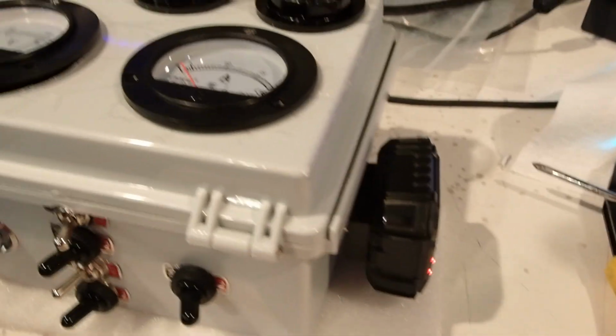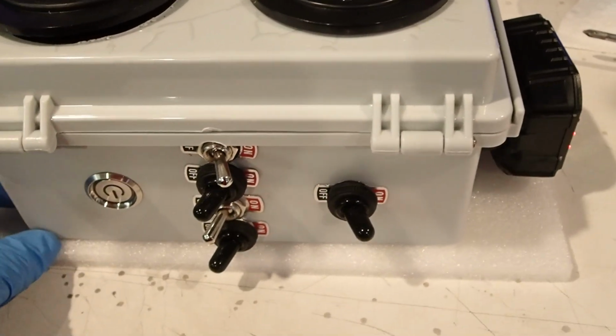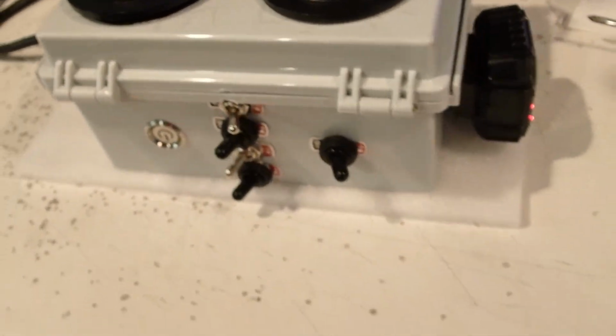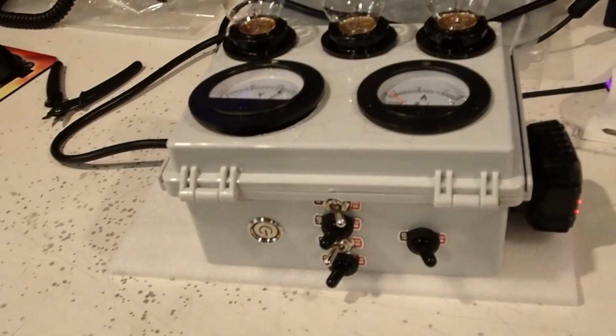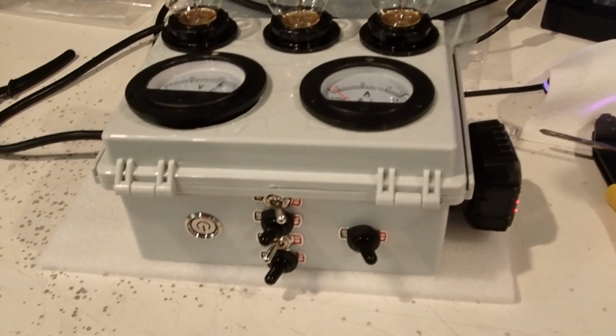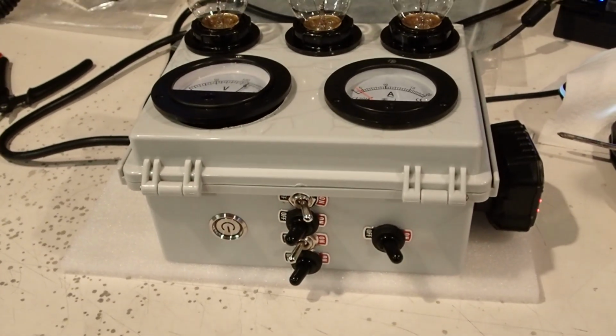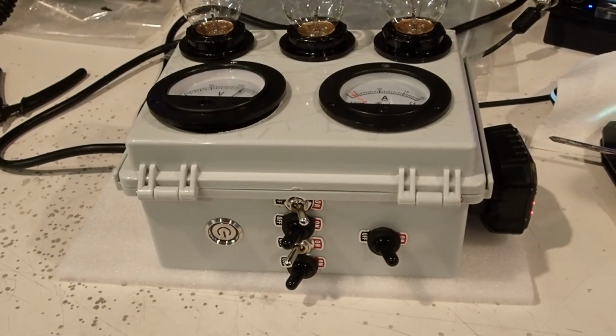It's important to remember this box provides no electrical isolation. To get isolation, you need to use an isolation transformer. So you use an isolation transformer, then a Variac, that plugs into this, and then the device under test plugs in over here.